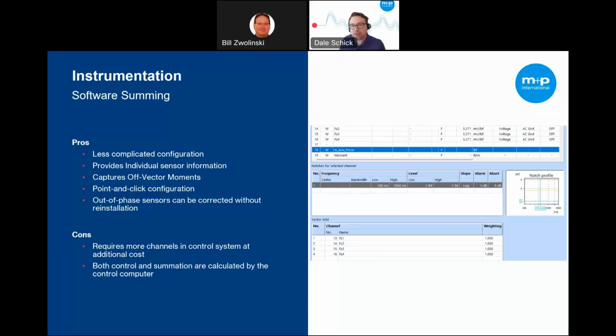Lastly, the individual channel limits can warn the user if a bad cable or sensor overload occurs. So if a single cable were to go bad during a test, this could either warn or abort the system because you're not going to be limiting to the full potential of the system.